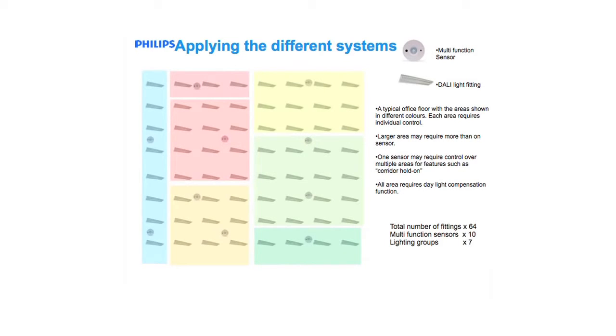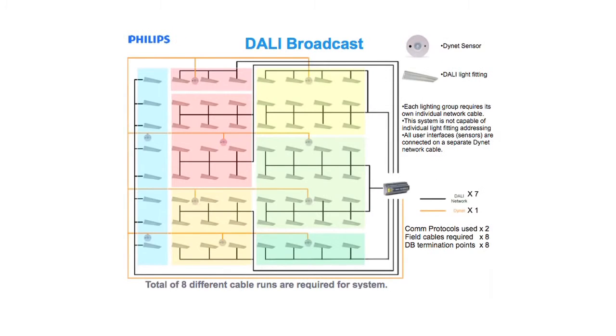The office floor plan shown before will be used again as an example to show the differences between DALI broadcasting, DALI addressing and DALI MultiMaster, showing how the three different systems apply to the same floor plan. This is so you can see the wiring requirements of each of these systems and why the DALI MultiMaster is such an advantage. This is the DALI broadcast system applied to the office floor layout example.